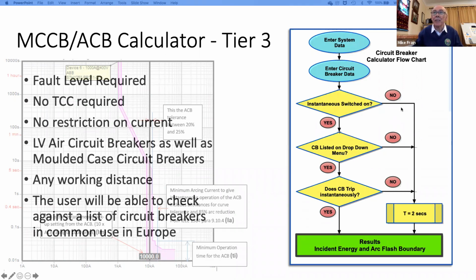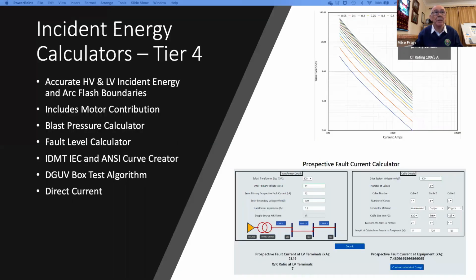Alternatively, if it's switched off, or the circuit breaker is not listed, or the circuit breaker doesn't trip instantaneously, then a 2-second disconnection time will apply, and then we still get a result, but it will be a massively increased result because it's based on 2 seconds, not an instantaneous one.